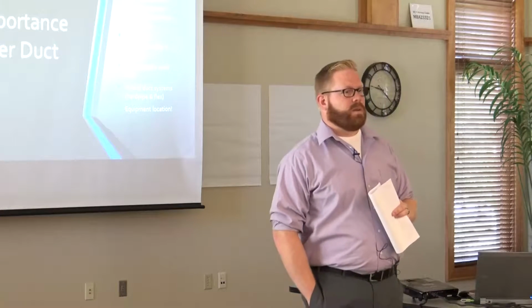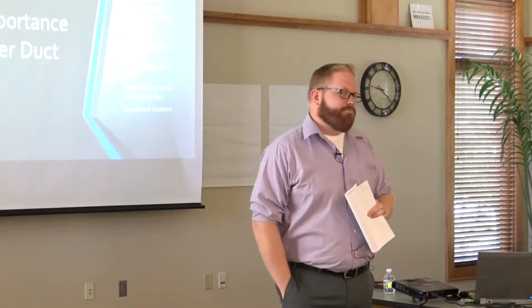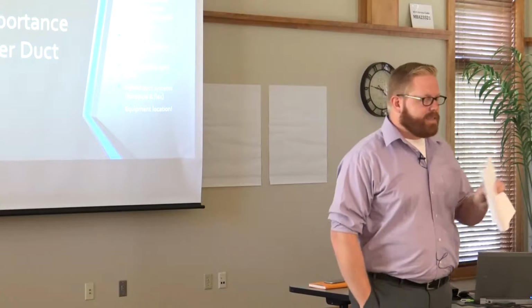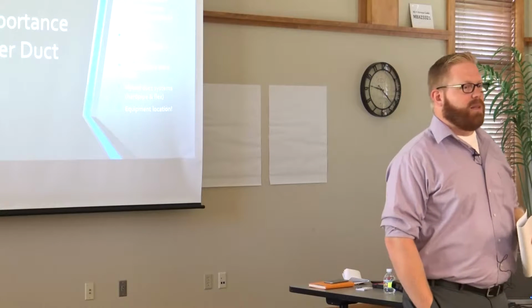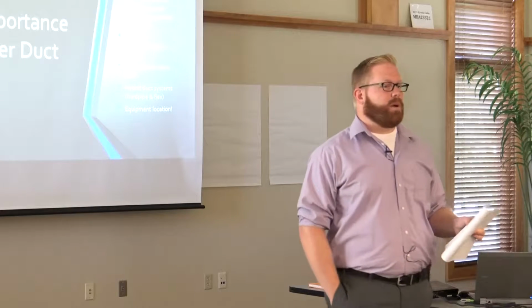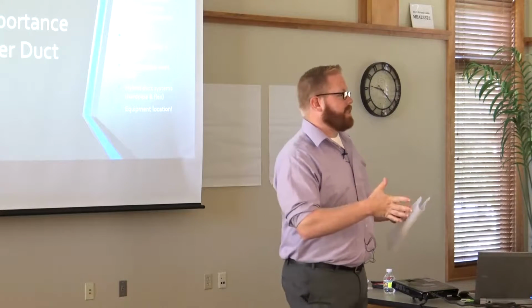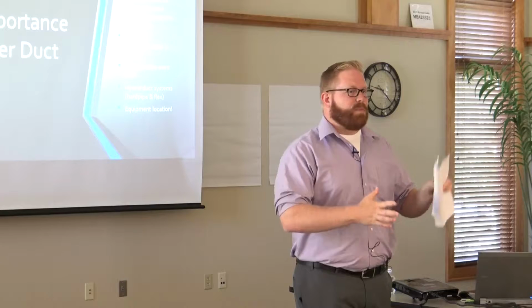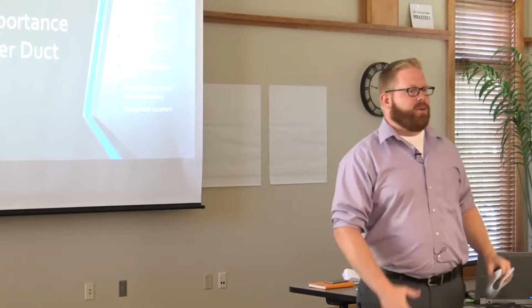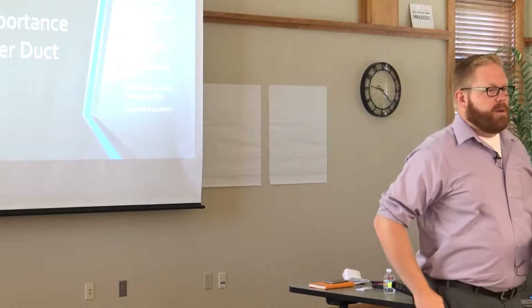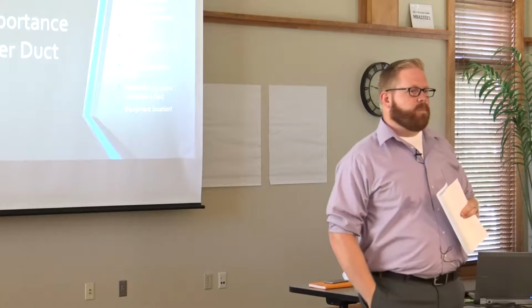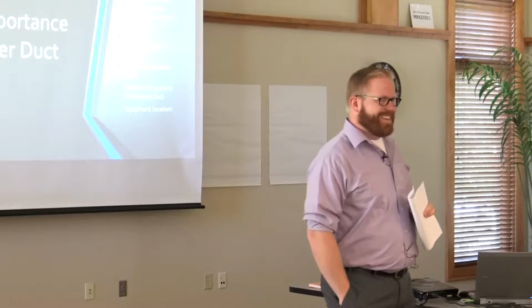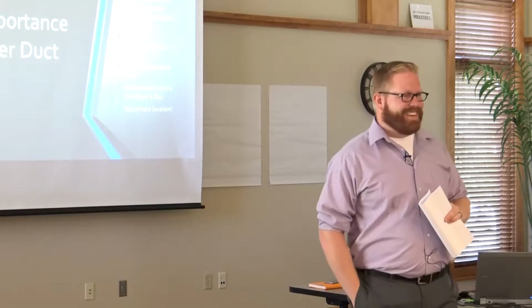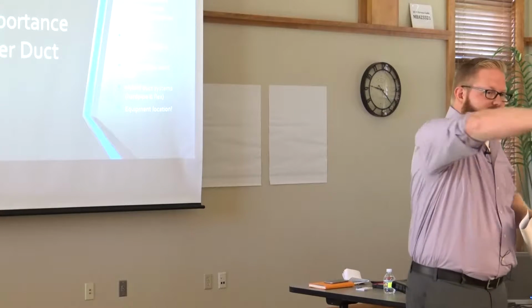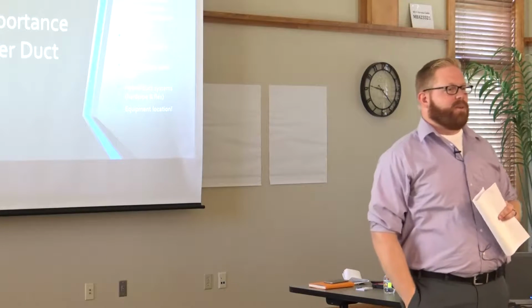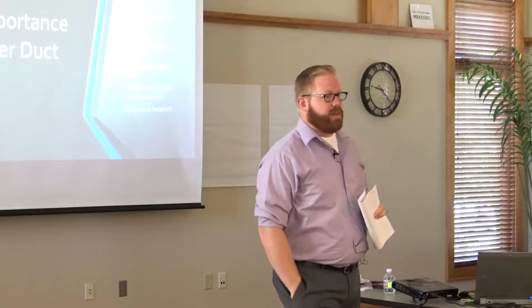Sure. And with 4-inch, I've done studies and tests on that before as well, and 4-inch certainly does reduce that number. Just because a bath fan says it's 110 CFM doesn't mean you're getting 110 CFM depending on how it's vented. And then the HVAC technician typically points the damn thing in the wrong direction. Right? Yeah, where you have to do a bend or a turn and you're losing that airflow coming directly out of the fan. You're absolutely right.